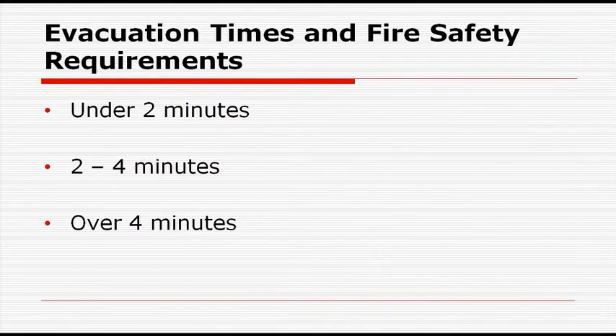Evacuation times and fire safety requirements. If a resident can evacuate in under 2 minutes, the following things are needed: a smoke detection system, and a sprinkler system only if required by the type of construction, number of floors, or class of the facility. If the resident takes 2 to 4 minutes to evacuate the facility, you need to have an externally monitored smoke detection system, vertical smoke separation between all floors, and rated stair enclosure. If the resident takes over 4 minutes to evacuate the facility, with or without employee assistance, there needs to be a sprinkler system, vertical smoke separation between all floors, rated stair enclosure, as well as 24-hour awake and qualified resident care staff.